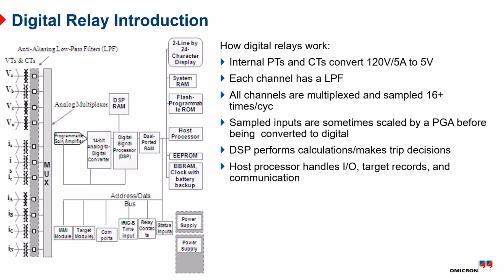Obviously, on the other side, you see the host processor. This is the processor that's usually programmed in C. It does all of the output, the binary output channels, so the trip outputs for a protective relay. Also measures the status inputs, like breaker position that comes into a relay, or a communication, or even a panel switch input that comes into a relay. So the host processor handles all that.